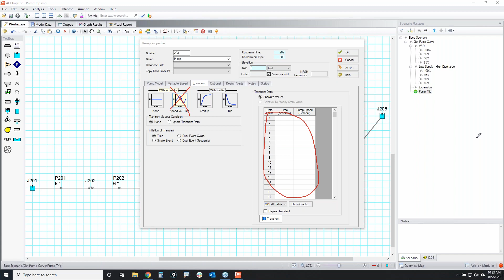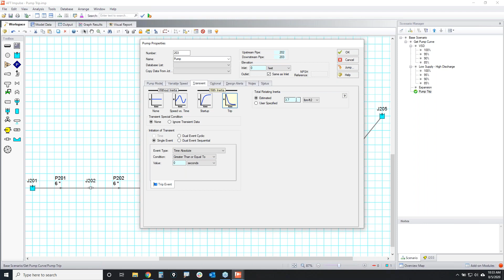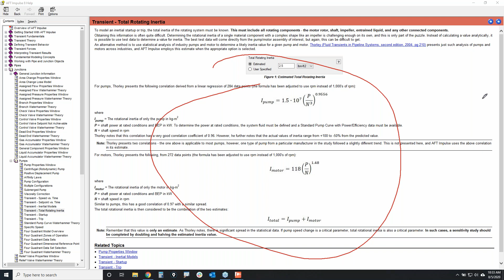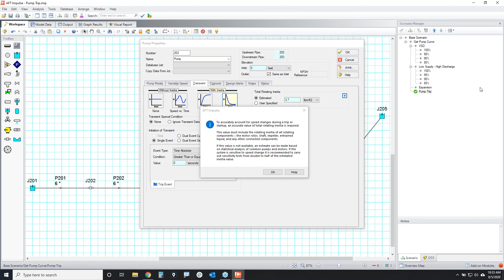But the thing is, if you know exactly how fast your pump comes up or down in speed and the profile in which it comes up and down in speed, you could enter that directly and it simplifies the calculations a little bit. However, we have some inertial models which are a bit more accurate because they actually will take into account the total inertia of the fluid, the motor, and the pump impeller. So if you know what the total rotating inertia is, you can specify that directly. But if you don't know what it is, you can click on estimated and it estimates a value for you.